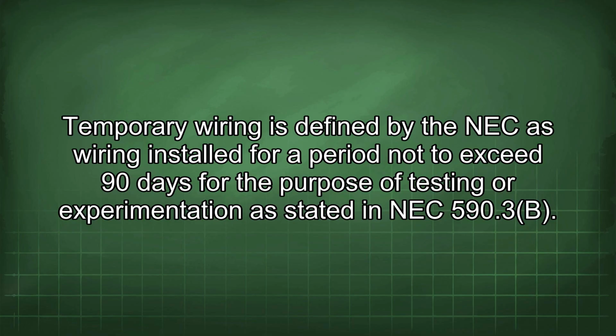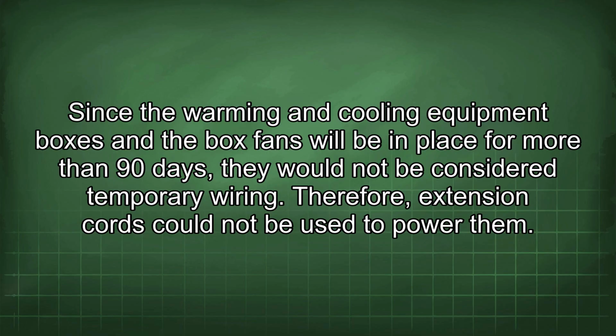Temporary wiring is defined by the NEC as wiring installed for a period not to exceed 90 days for the purpose of testing or experimentation, as stated in NEC 590.3(B). Since the warming and cooling equipment boxes and the box fans will be in place for more than 90 days, they would not be considered temporary wiring. Therefore, extension cords could not be used to power them.